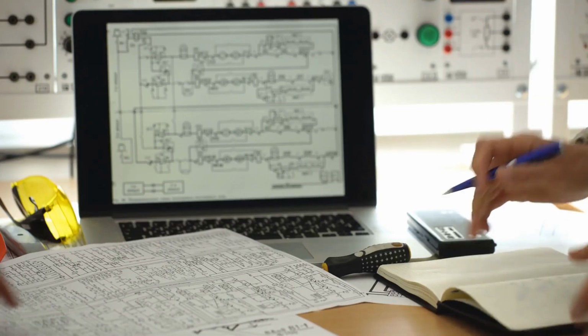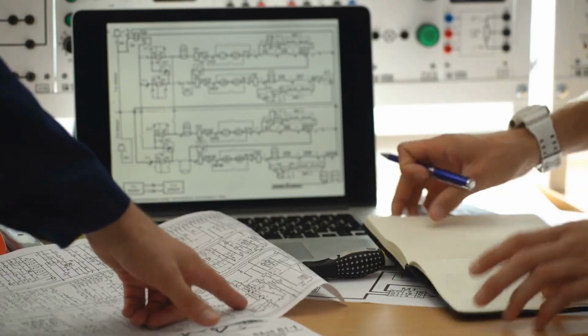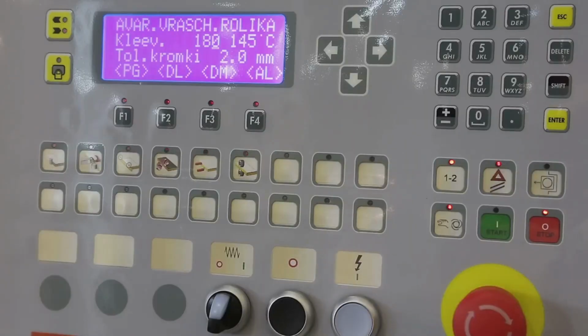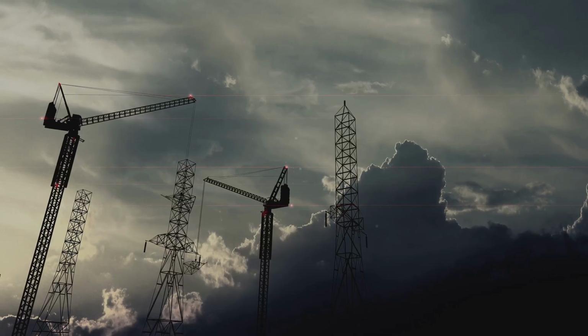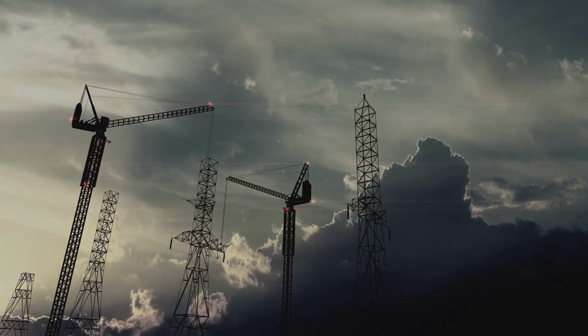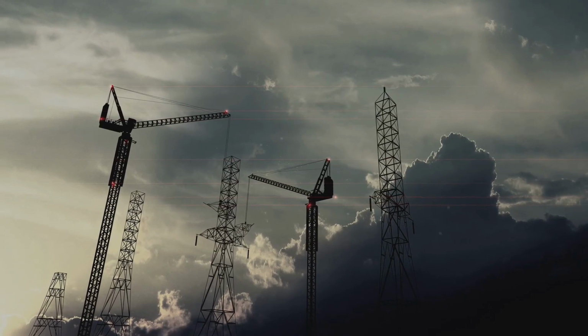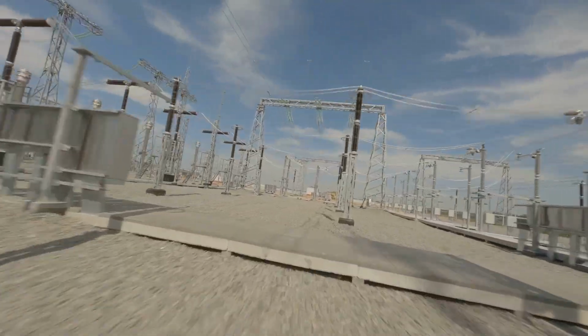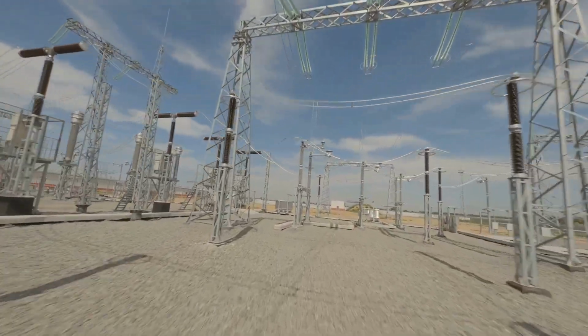Clause 5.3, Prioritization and Conflict Resolution. Sometimes DERs receive multiple control requests: voltage regulation, frequency control, and protection activation. IEEE 1547 resolves these potential conflicts with a prioritization logic. Ride-through obligations always take precedence over power quality control.